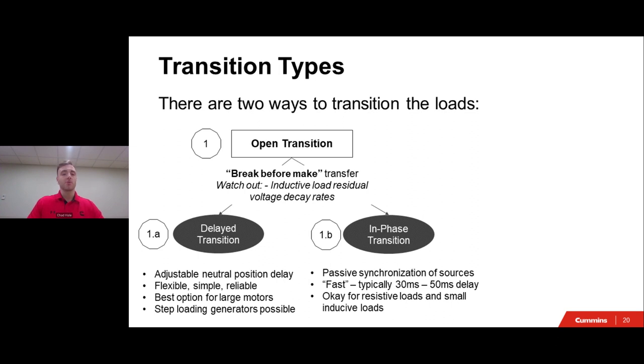This means that the automatic transfer switch is breaking connection to one of the power sources before making a connection to the other power source. So for a period between the disconnection and the connection, neither the normal power source nor the emergency power source will be giving electricity to the loads. So they will have a break in power. To dive a little deeper into the open transition types, there are two types. Those two types being open delay transition and open in-phase transition.